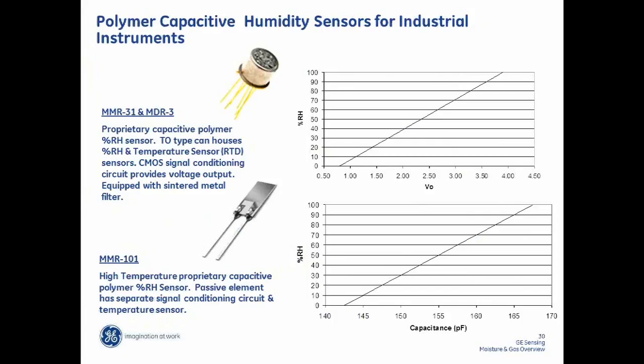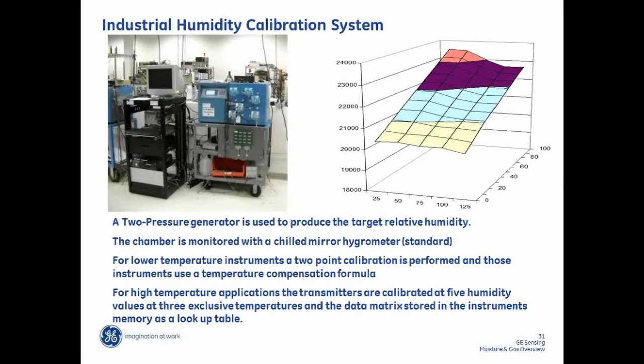Well, in any regard, these sensors will put out a signal, and they're designed for higher levels. We calibrate them by putting them in a test chamber, a two-pressure chamber referenced to a chilled mirror. On our lower temperature sensors, we only have to do a two-point calibration, and that sensor uses a mathematical relationship for temperature compensation. So by measuring the temperature, we just are running an equation to correct the sensors to read the correct relative humidity. For the high temperature, we plot out essentially a matrix. We run the sensor at 5 different humidity values at 3 different temperatures, and essentially plot that into the unit's microprocessor as a lookup table. So it becomes a calibrated system over that full array of temperature and humidity.